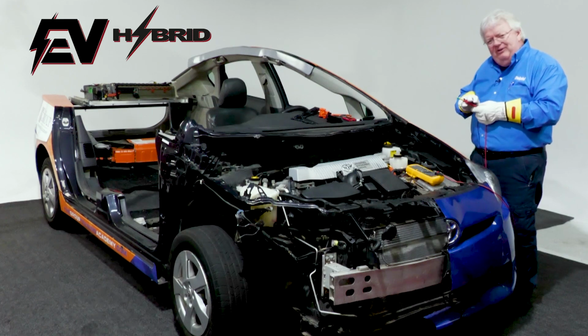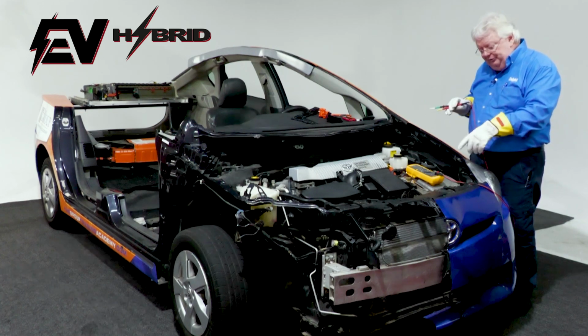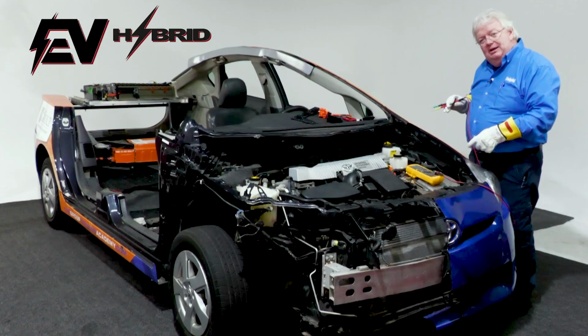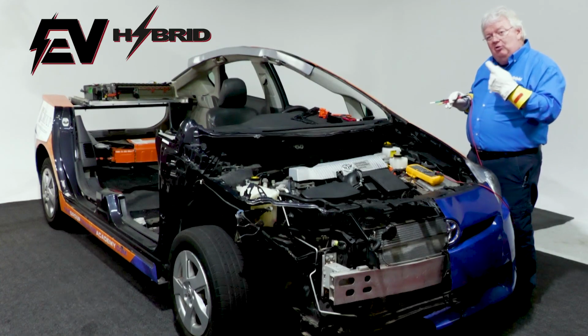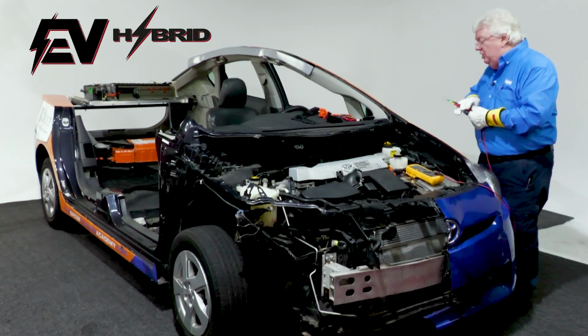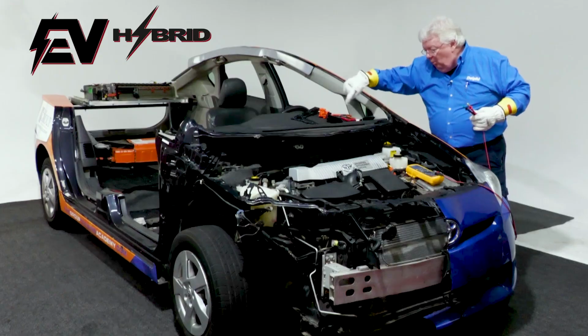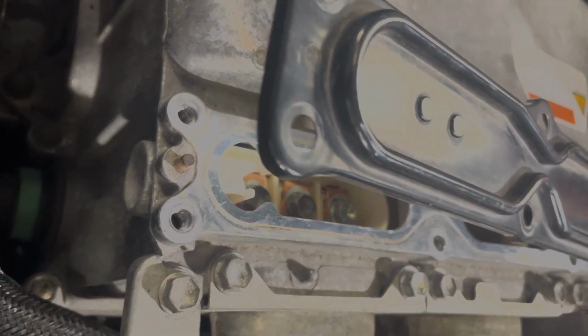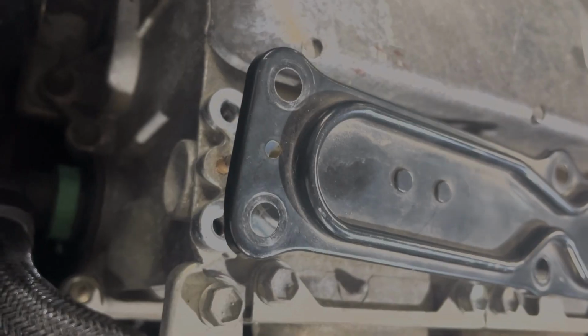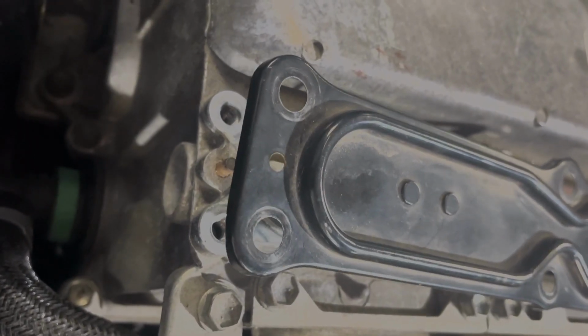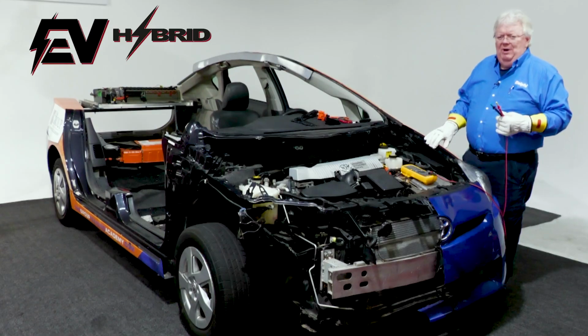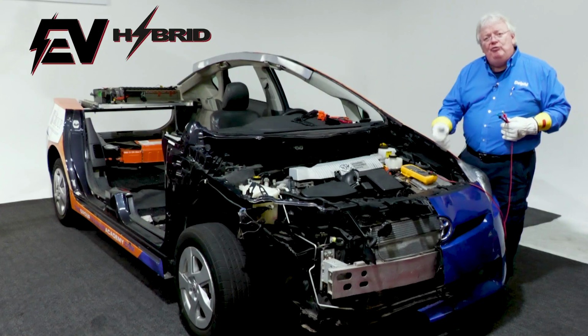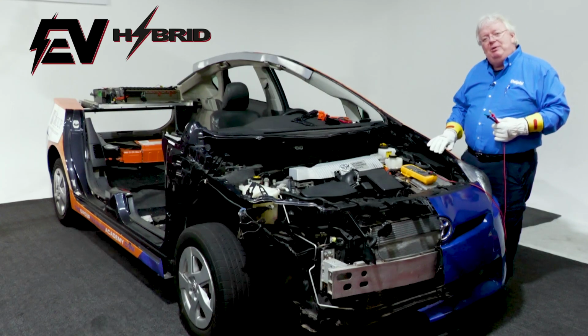So in this case, it's very similar. It's 12 volts on this particular connection, power to one terminal, ground to the other, and when this cover with the white interlock shorting bar is installed, that voltage then drops to 0. That's how it's supposed to work. If you saw voltage and thought, how can we short something out under here? It's low voltage. It's not an anomaly. It's supposed to work that way.